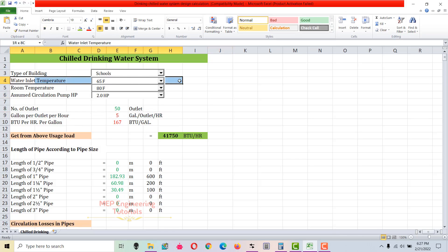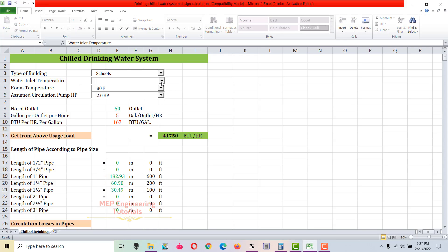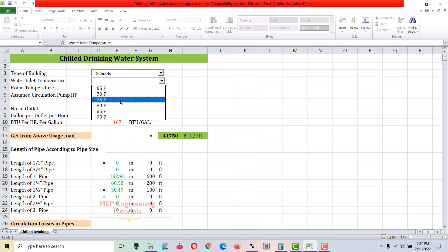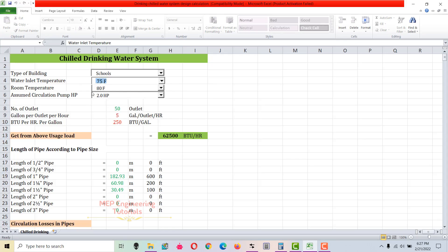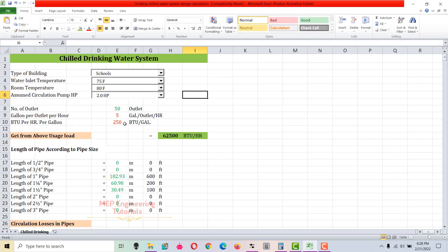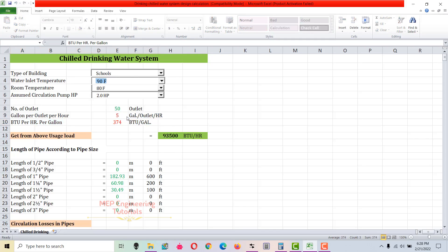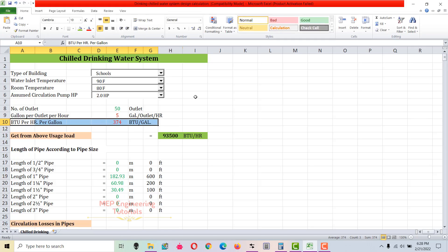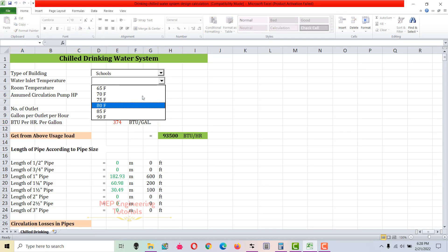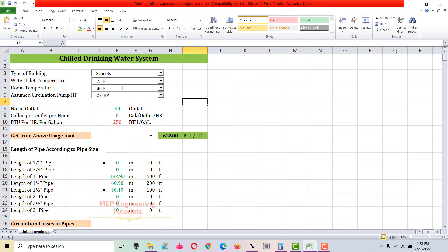The second thing is the water inlet temperature. You have to check this from the local authorities of your area. I'm going to use 75°F water inlet temperature. If I change this to 75°F, the BTU per hour per gallon value will change. This BTUs per hour per gallon depends on your water inlet temperature — if I change it to 90°F, this value changes to 374 BTUs per gallon. So I'm going to use 75°F.